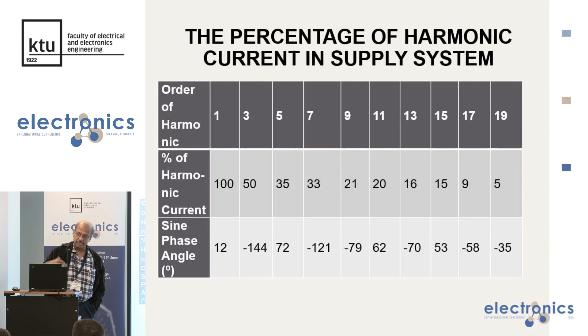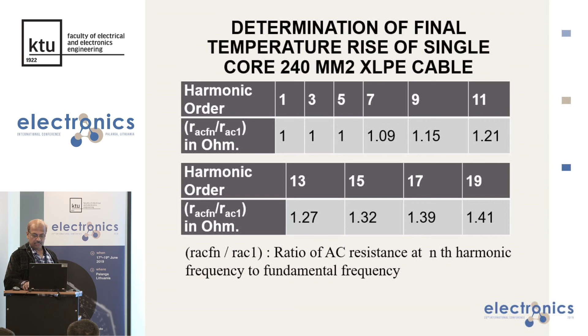Here is the determination of final temperature rise of a single core cable; it is presented for a 3 core cable. The 3.5 core cable we have already studied in the laboratory, and the experimental validation is already done. The determination of final temperature rise of a single core cable is the same. Different formulas are available for this empirical analysis for the 3.5 core, single core, and 3 core cables. The main thing is the final temperature rise due to harmonic frequency in degrees centigrade, and that will affect the life of the cable.